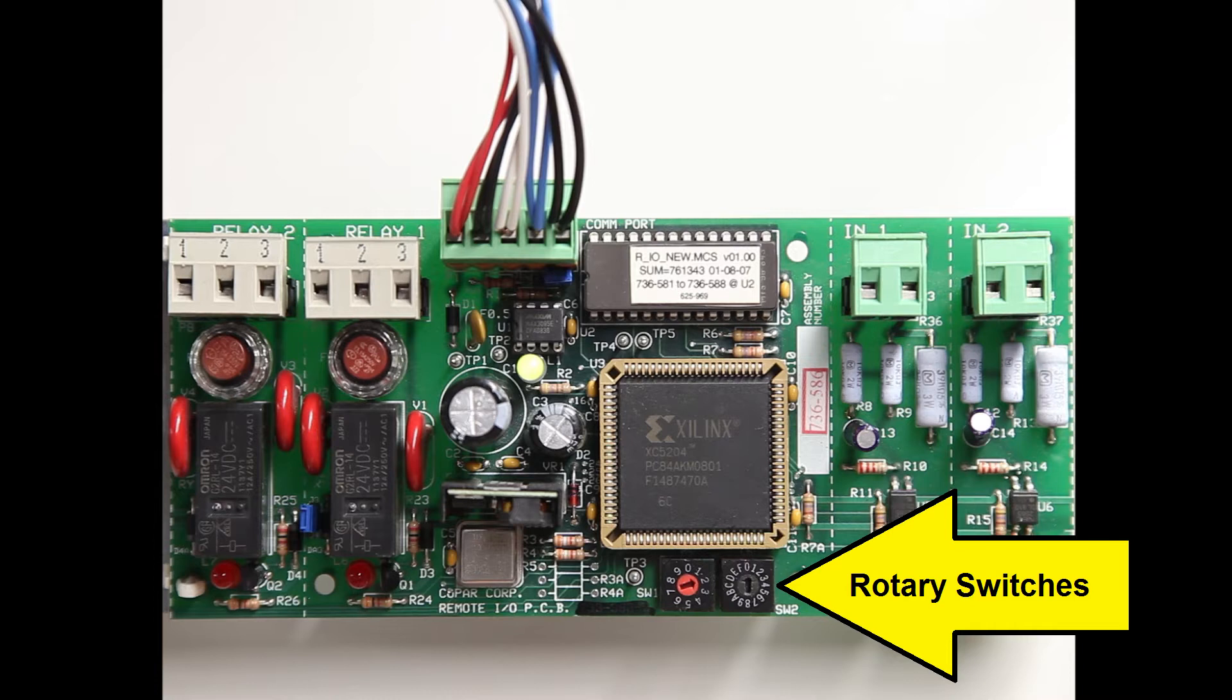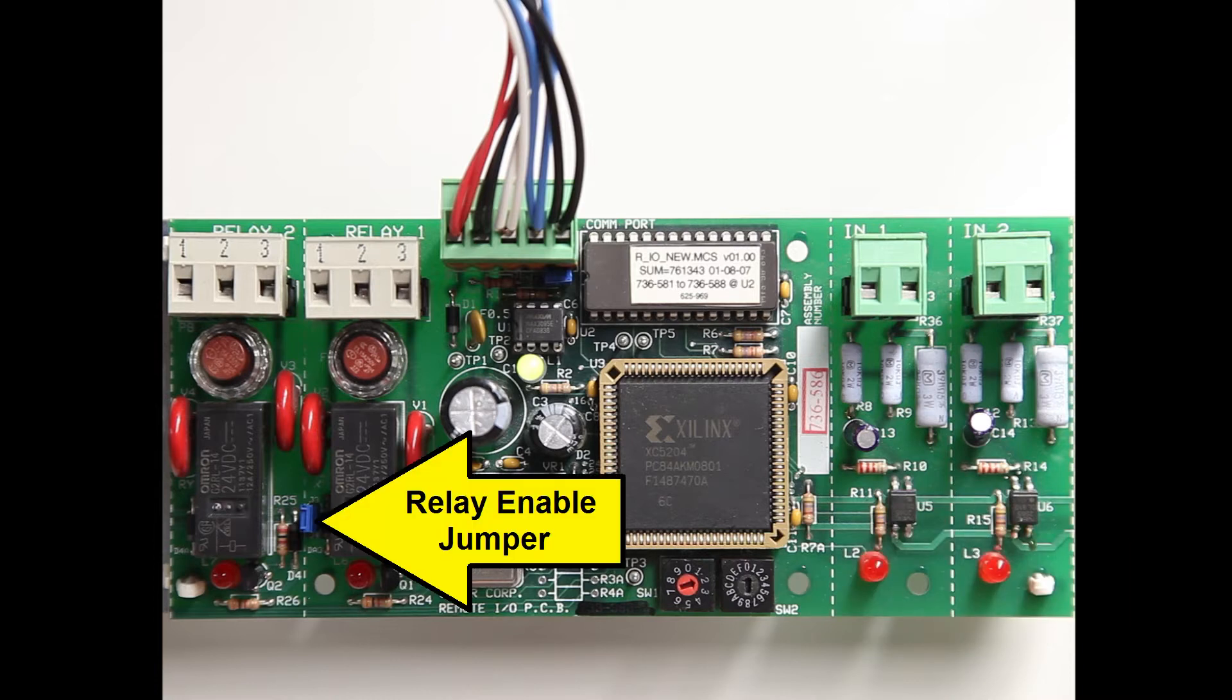These two rotary switches are used to address the card. Some cards, such as this one, also have a jumper which enables the relays. Normally, this jumper should always be on. Removing the jumper prevents the relays from functioning.